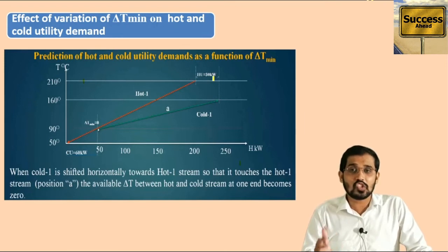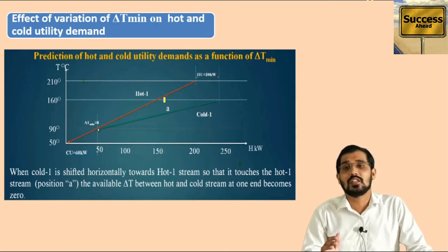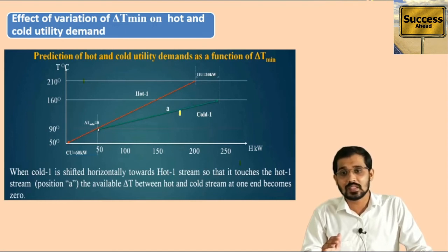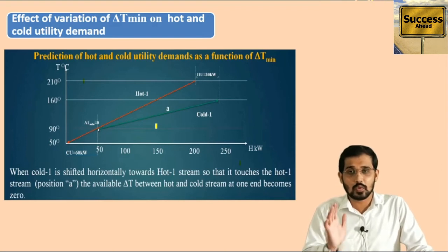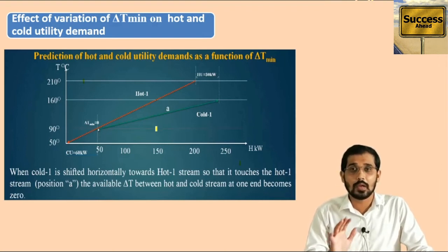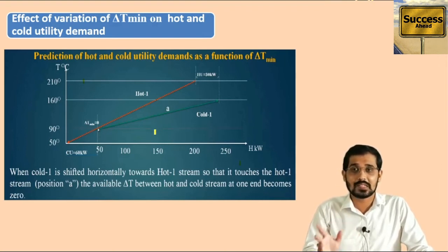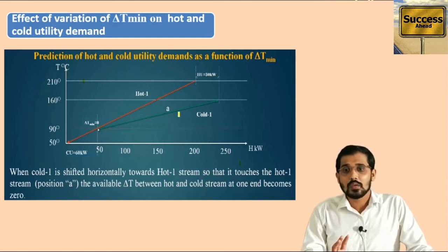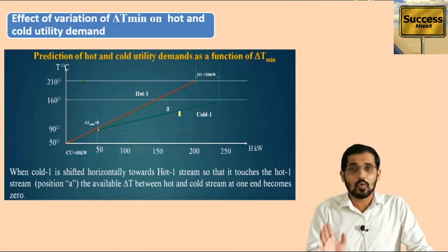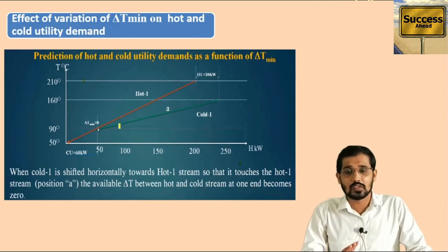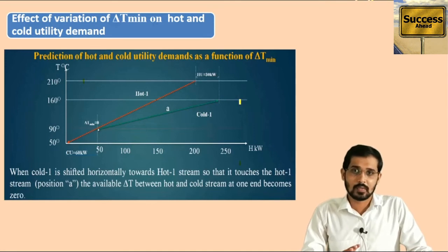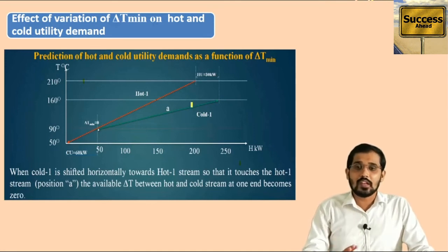Similarly, there is an extra part of the cold stream at the top. To heat this extra part of the cold stream, extra hot utility is required because the hot stream is not available there. That extra hot utility value is Hu, which is 30 kilowatts. This value can change if I move the cold stream away from the hot stream — only horizontal shifting is possible, not vertical. I will show this variation in the next slide.